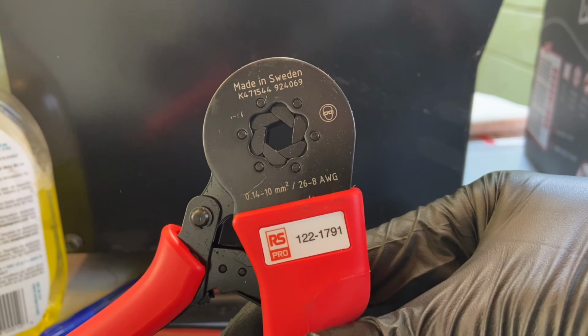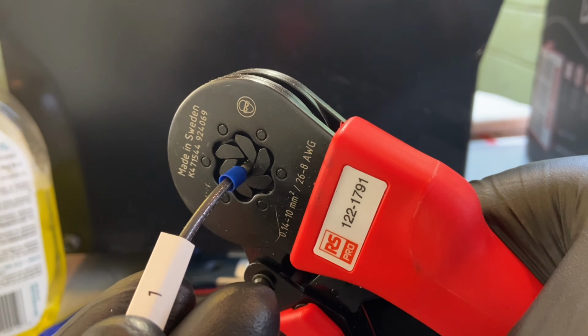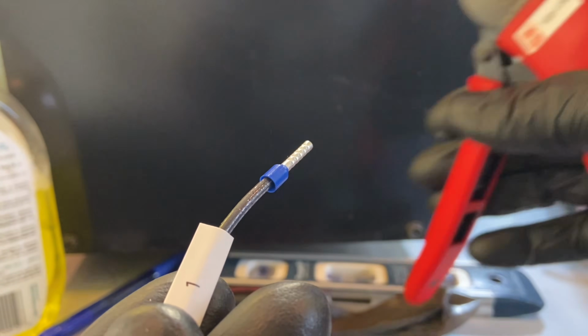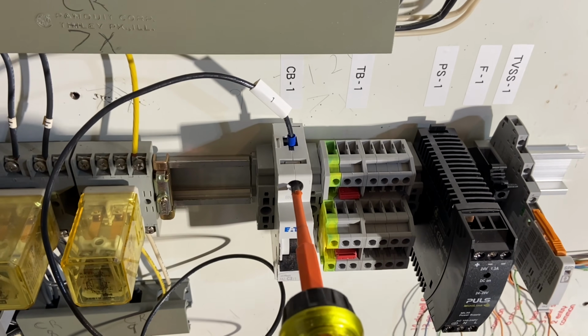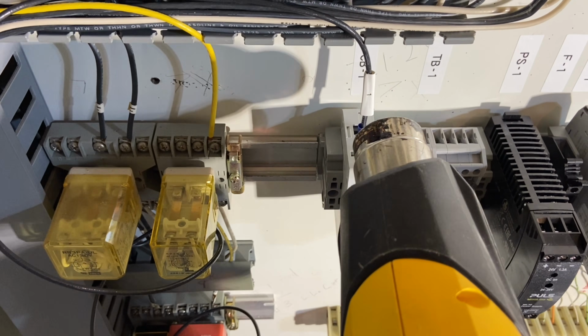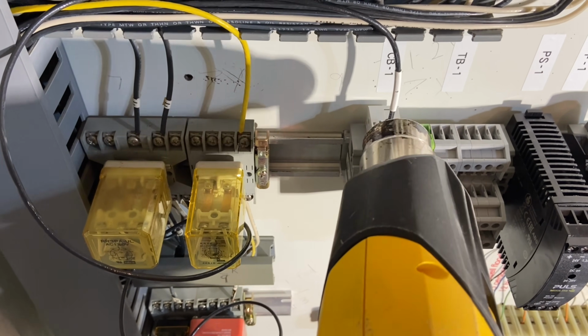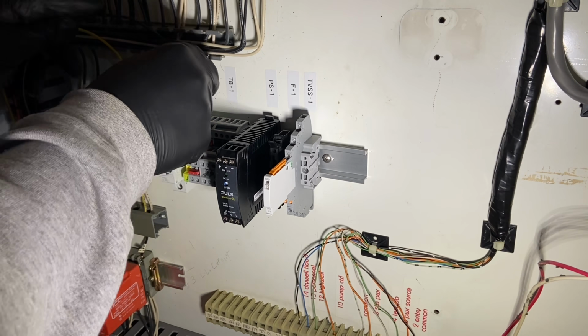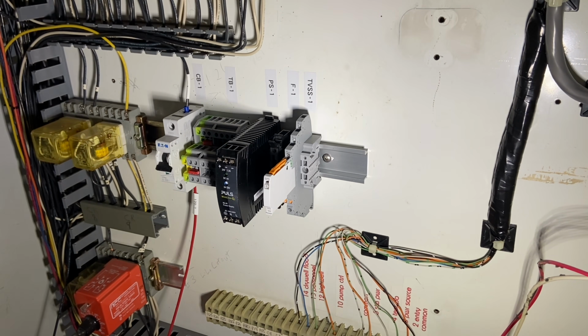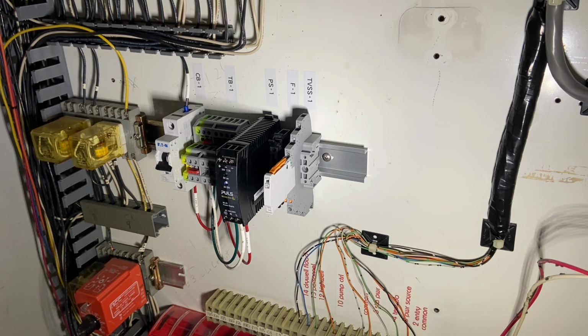There are many different styles and brands and pressure ranges of transducer, but it doesn't really matter what you use as long as you know what your ratings are. So even if I replace this in the future, I could use a different brand. As long as I get another 0 to 15 psi transducer, I won't really have to change hardly anything. But even if I do get a different pressure range, I just have to change the scaling.